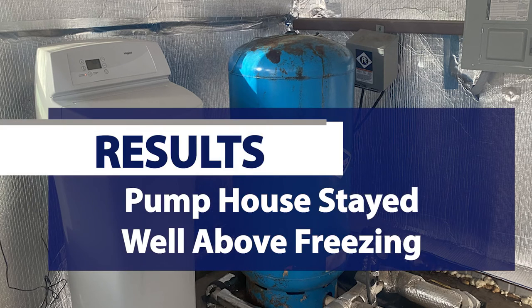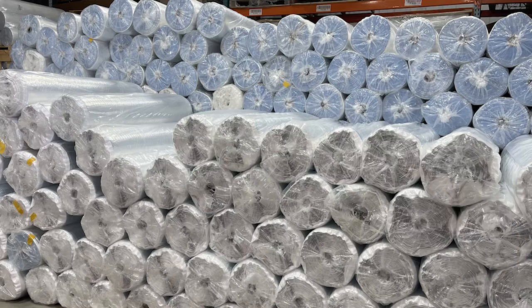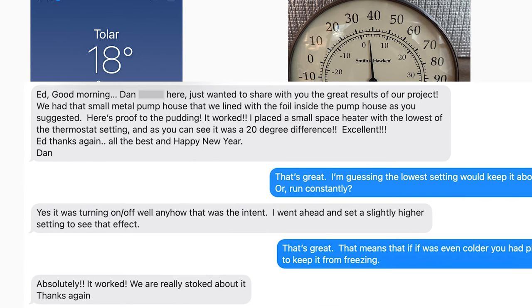So what were the results and how well did it work? I received this text from the customer one morning when it had been 18 degrees. He said: 'Ed, good morning, Dan here. I just wanted to share with you the great results of our project. We had that small pump house that we lined with the foil inside the pump house as you suggested. Here's proof to the pudding — it worked. I placed a small space heater with the lowest of the thermostat settings, and as you can see, it was a 20-degree difference.